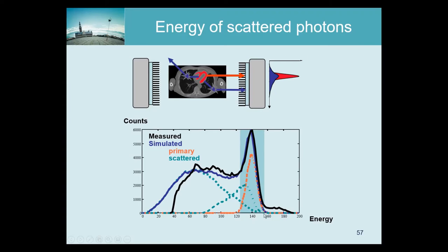So for example we can use this window here indicated by that shaded rectangle, but if we do that you see that there is a significant contribution of scatters. We could make the window smaller, but then we would see fewer trues. Okay, and so this tells us that the contribution inside the primary window is dominated fortunately by primary photons, and then the next important contribution is photons that scattered only once.